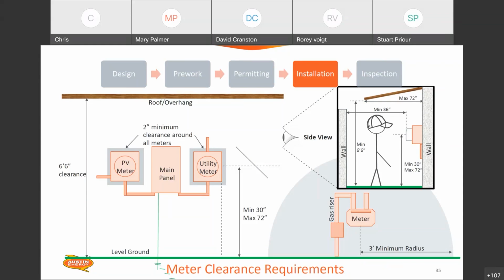Pay close attention to the service, like we've mentioned. The existing service will need to be brought up to code. If there's anything egregious or unsafe, pay close attention, particularly to the grounding electrode system. If we're on site and you're doing a standard solar installation, but we find that the old panel is not grounded properly and not bonded properly, we will make you bring that up to code in order to be safe. So pay close attention to that, because that might be something you need to address with sales and the homeowner at the beginning of the project. Because at the end of the project, nobody likes to hear it.